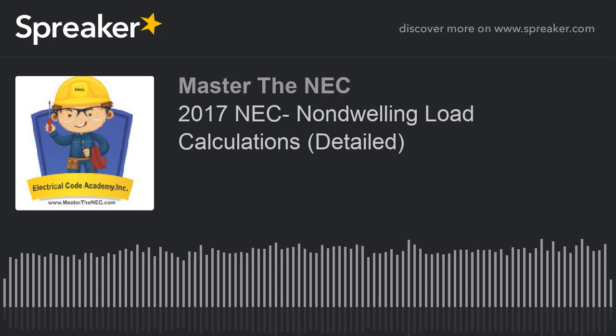Okay, hospitals, I can get a break, but I can't get a break in those areas where I'd have continuous loads, or the lighting would be on at all times, like ballrooms, dining rooms, operating rooms. Then we know the loads are going to be on continuously 3 hours or more. Those aren't really what you're using this table for. And in fact, you can't apply the demand factors of 220.42 to continuous load applications.